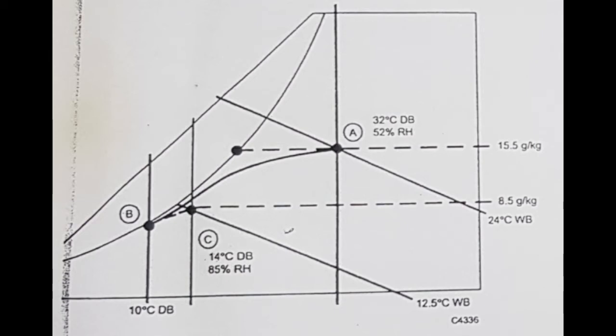Point number two: Air that contacts the spray droplets follows the saturation curve to the spray temperature 10 degrees centigrade dry bulb, point B, and then mixes with air that did not come in contact with the spray droplets, resulting in the average condition at point C.